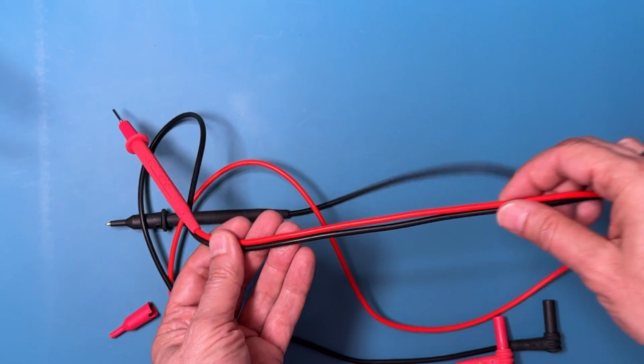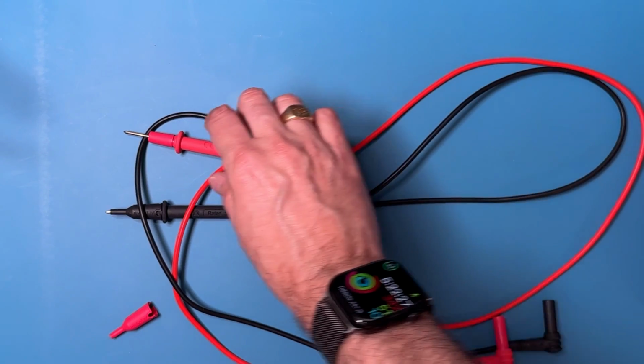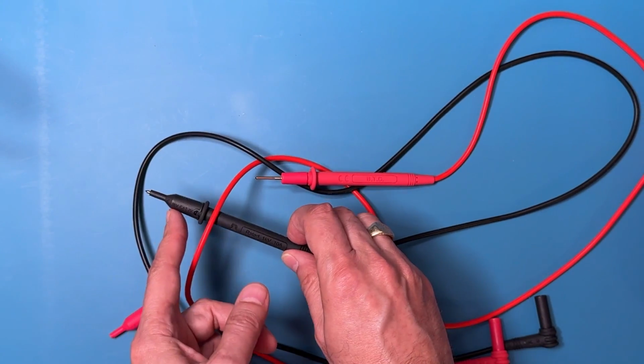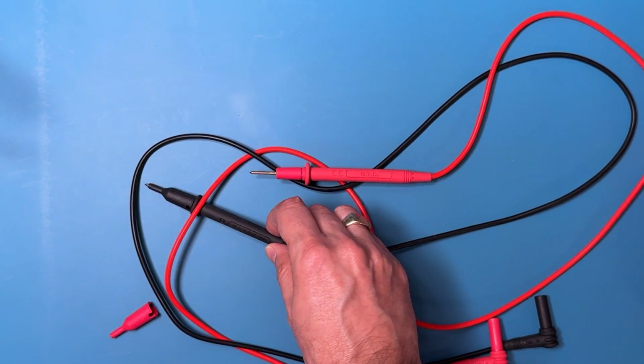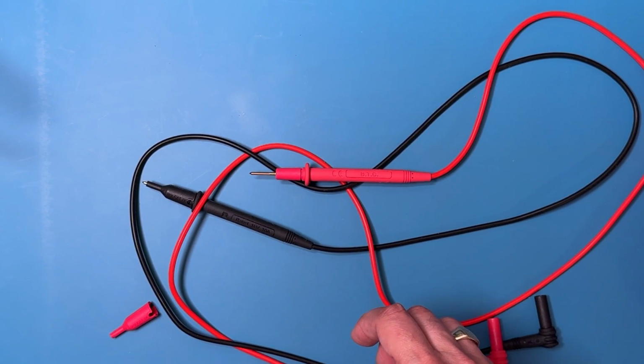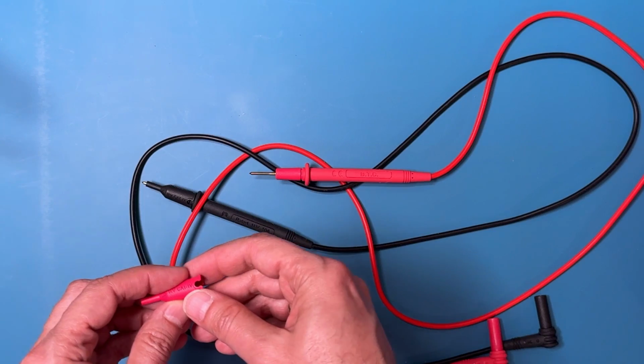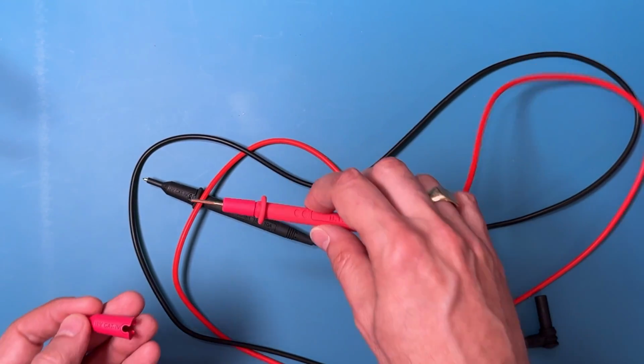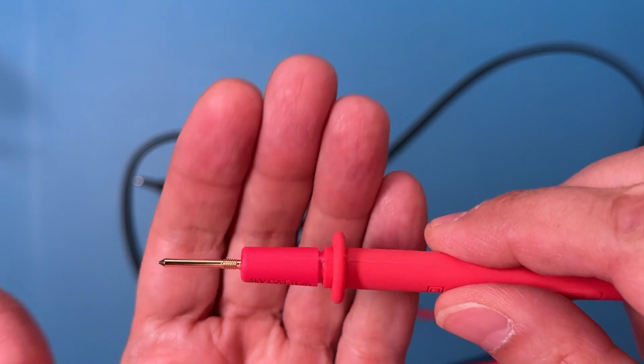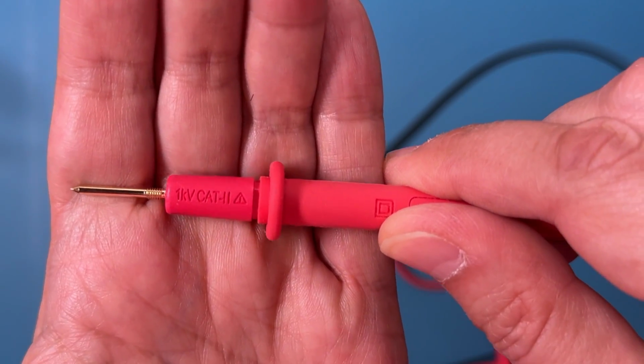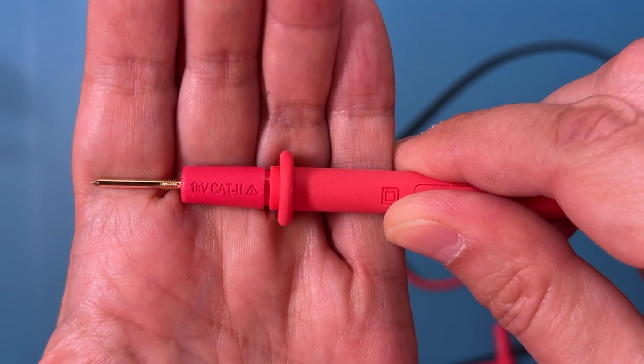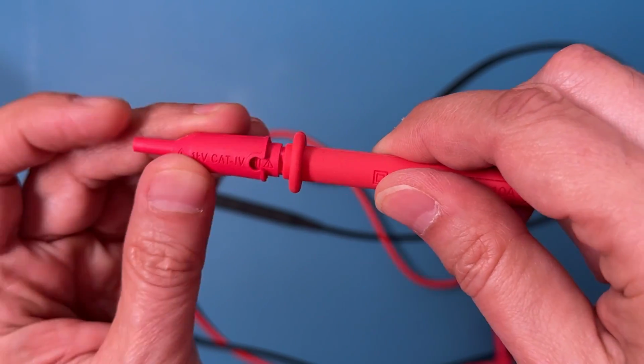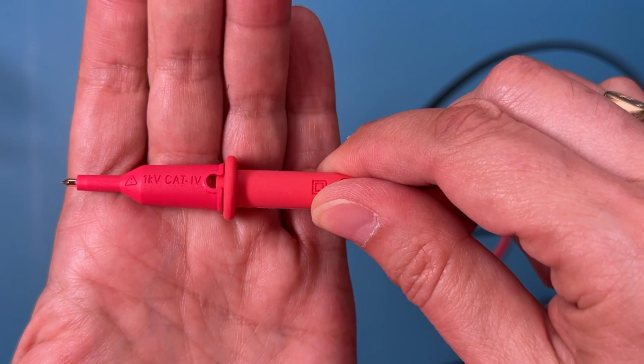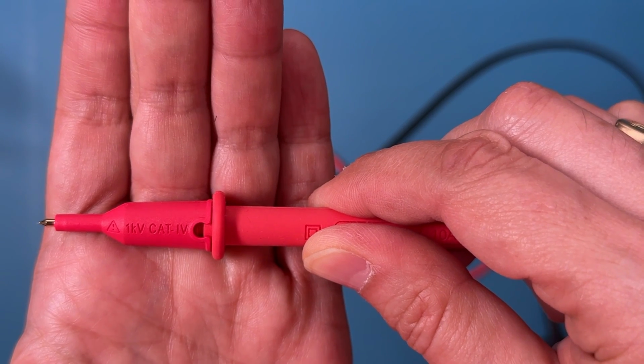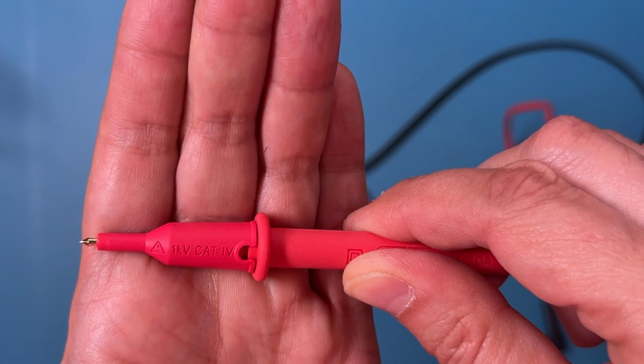This includes the gauge of the wire that's used for test leads and insulating covers or shrouds that are placed over the exposed metal. At higher voltages, electricity will travel across small air gaps between two conductors. This is called arcing and is very dangerous. These covers are meant to reduce the amount of exposed metal in order to prevent arcing. And we can see this lead. You can see that. That's rated at Cat 2 without the shroud. And if we put this shroud on, now, if you can see that, that's rated for Cat 4 with that little tiny bit of exposed metal at the tip.